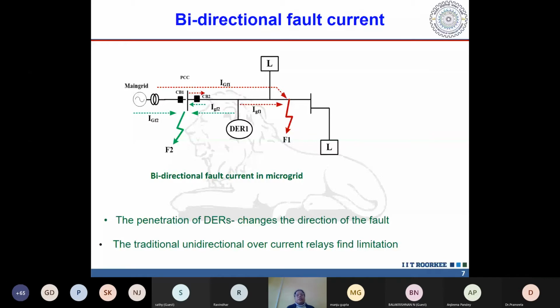This happens because the fault position has changed, so the current reverses direction. Instead of flowing from upstream to downstream, it flows from downstream to upstream. This is known as bidirectional fault current. During this reversal process, the angle changes significantly, almost a 180-degree change, and of course the magnitude also changes, though the angle is mostly affected.